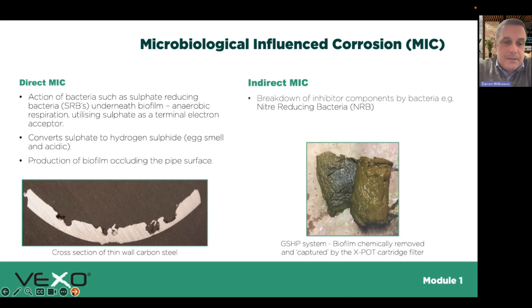It will feed bacteria. Again, giving an anecdotal example, I was walking around a project. I said, how's the water quality? I was told no major issues apart from October. We turn things on, we get a few pump seal failures and a few radiators leaking. So I explained whether that can be avoided. And I said, anything else? He said, oh yeah, we top up loads of nitrite as we look to shut down the heating, to make sure it's got plenty of inhibitor.